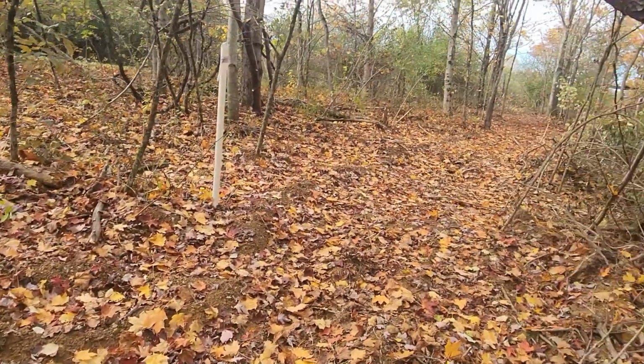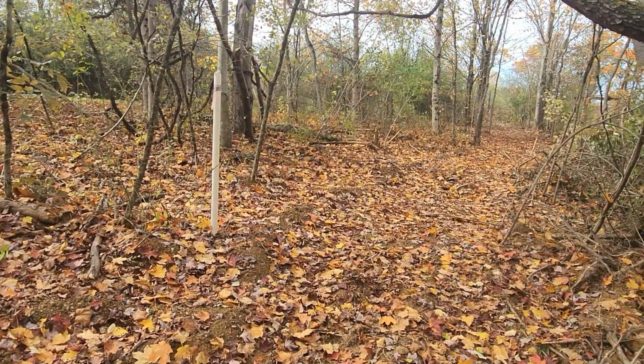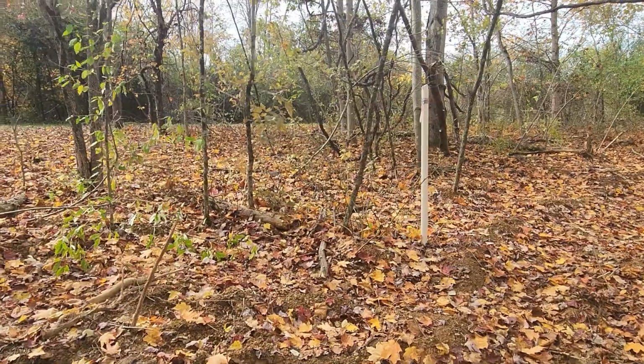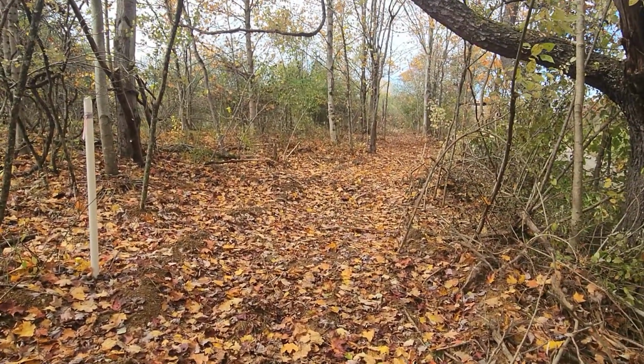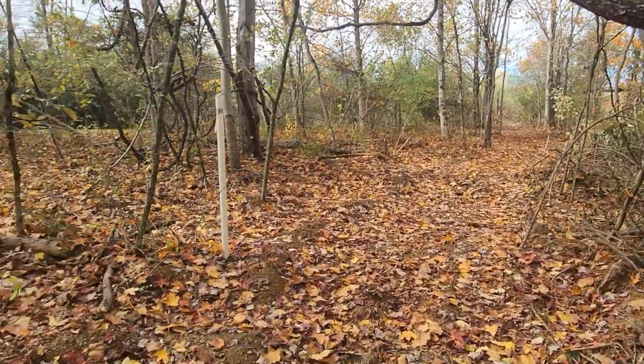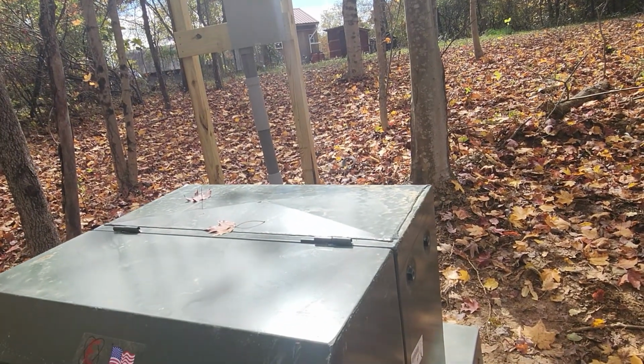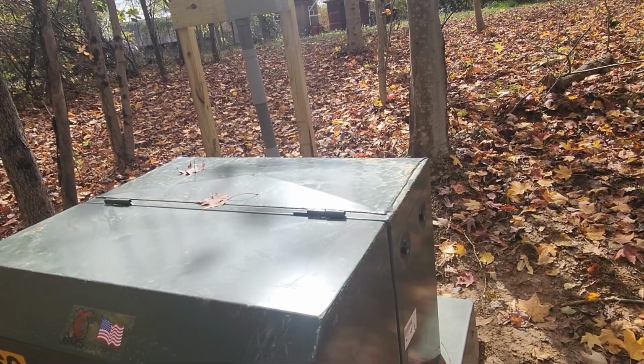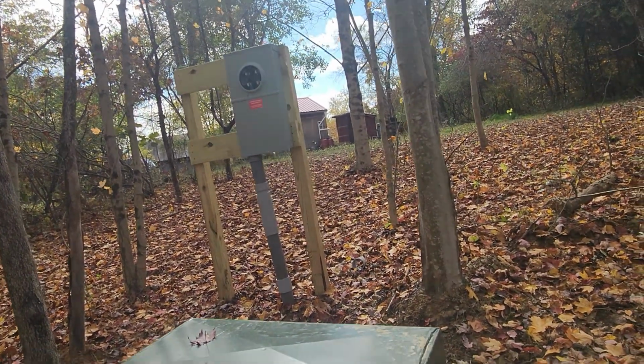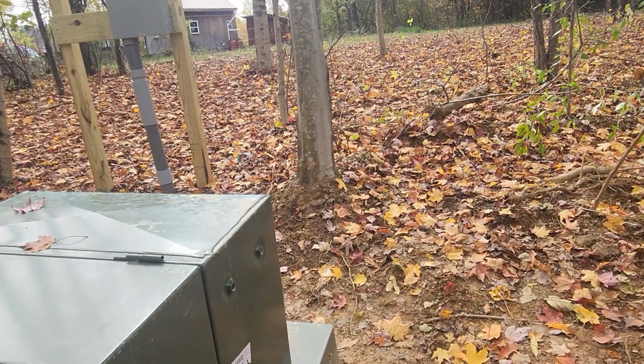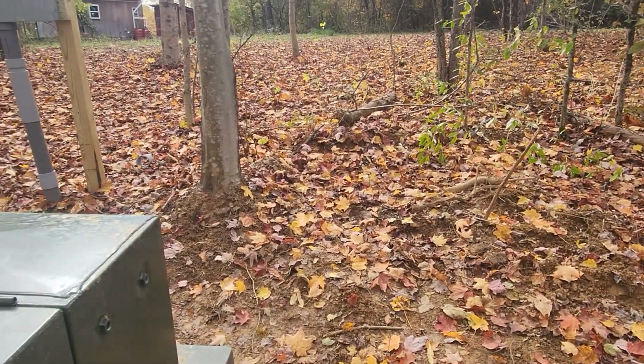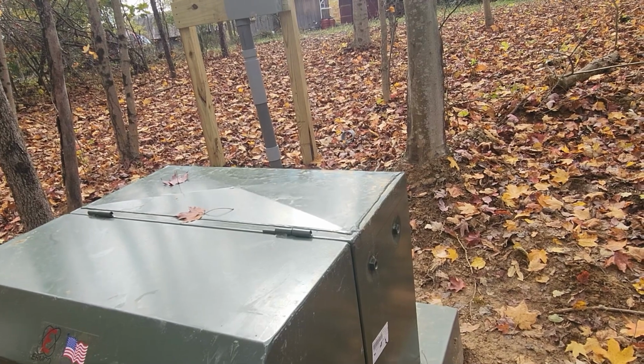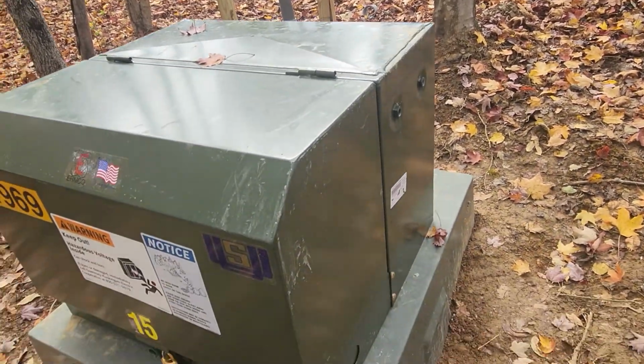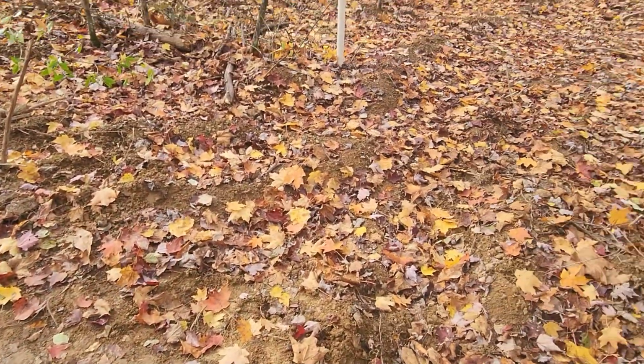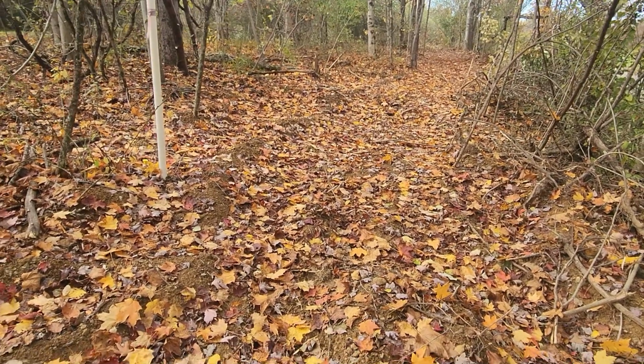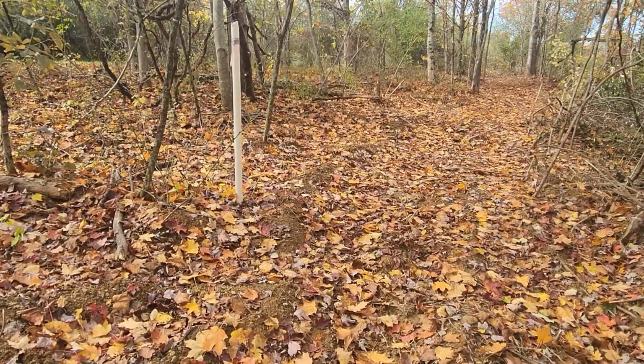They won't guarantee 200 amp service over 150 feet, and I'm 280 feet from that pole. So what they had to do is bring their high voltage line down here to this transformer, which converts it to 200 amps and sends it to the meter base. That's why you have to have transformers, for transmitting high voltage and then cutting it down to what you need for the box. And I have to come off the top of the pole for the high voltage lines, not the regular. So if there was a pole closer, I wouldn't have had to have done this.